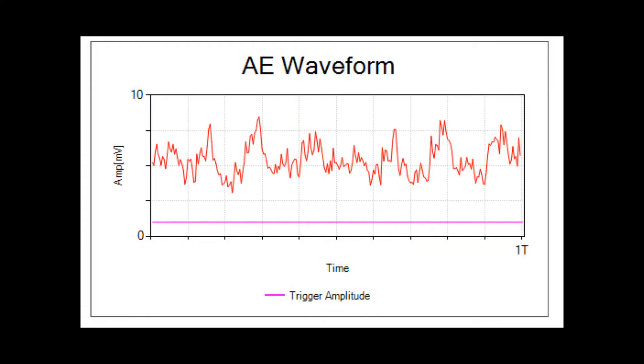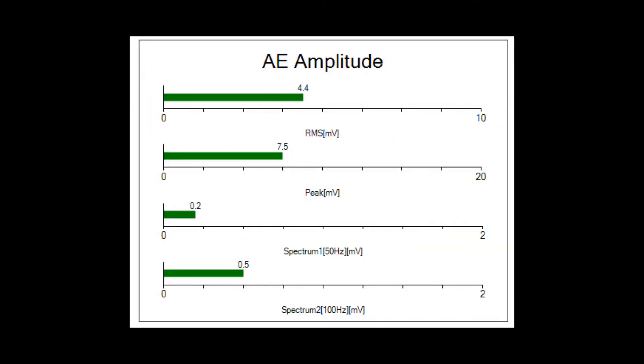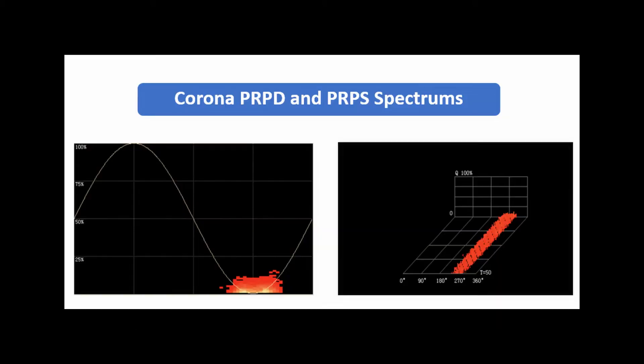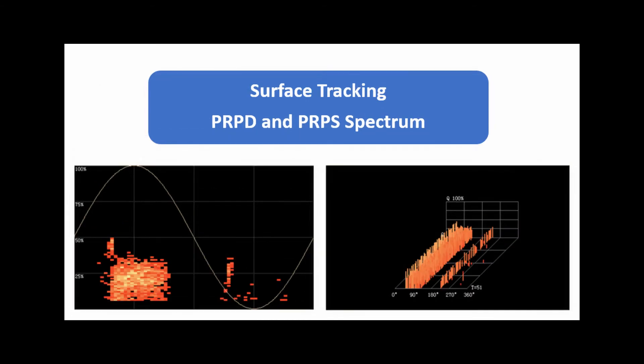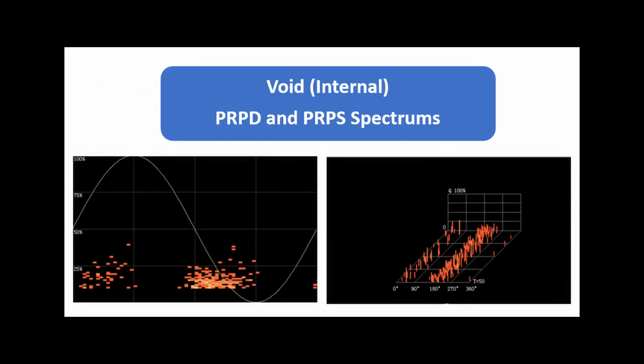The core issue for analyzing the severity of a PD signal is first determining the PD type. PMDT utilizes PD type determination techniques based on time domain spectrums. Each PD type has typical characteristics which are useful in determining the PD's developing progress and severity level.